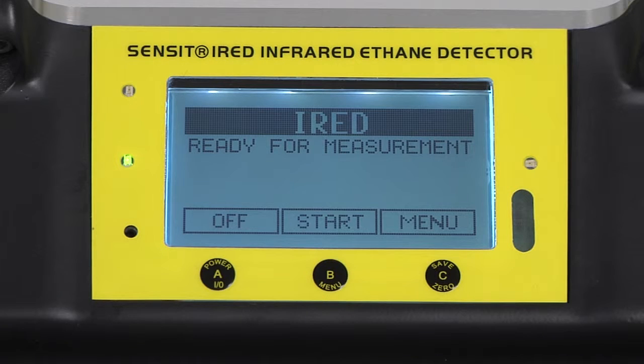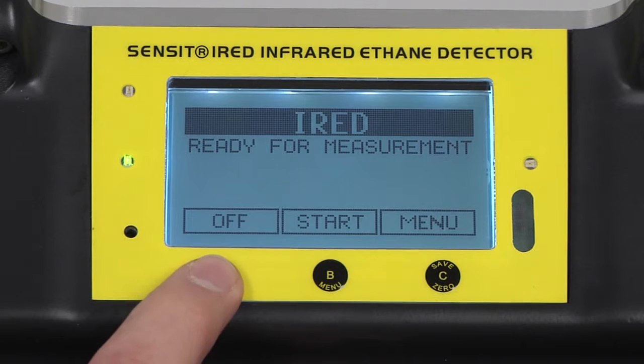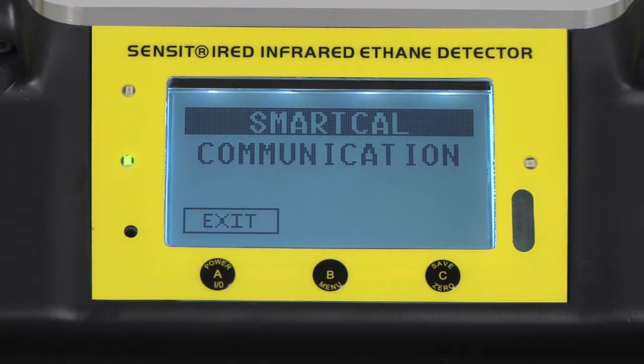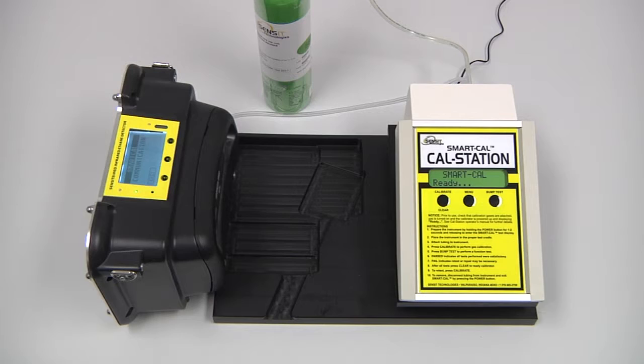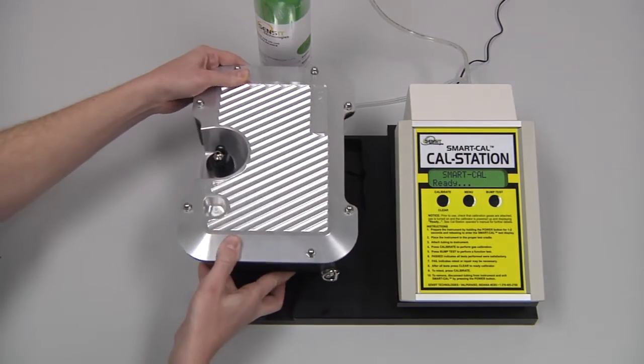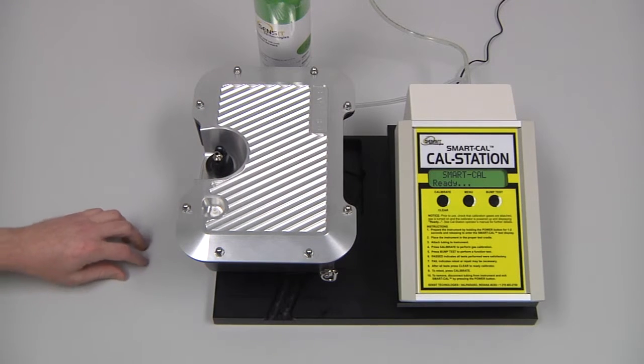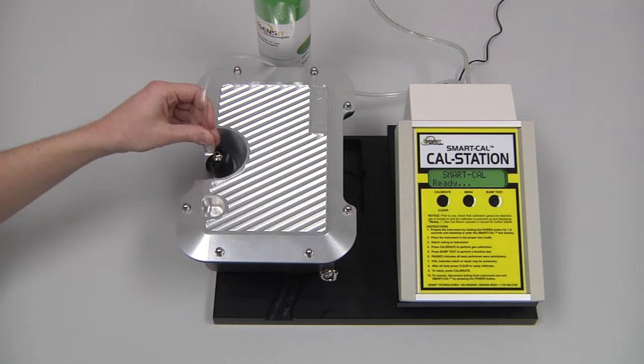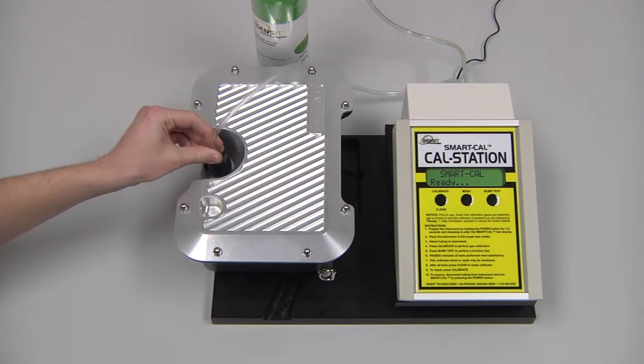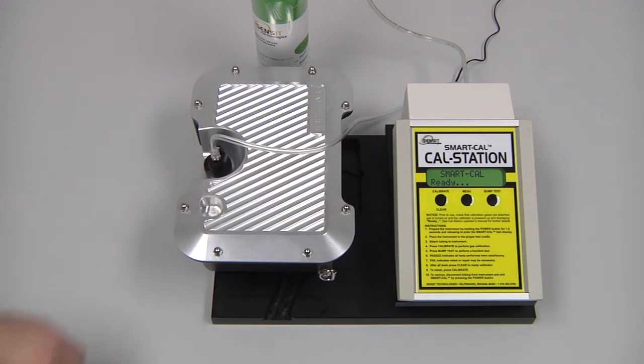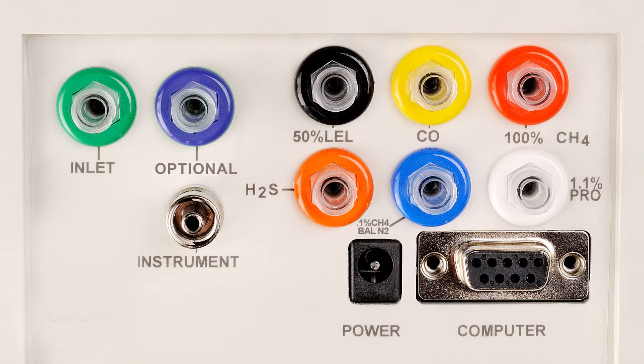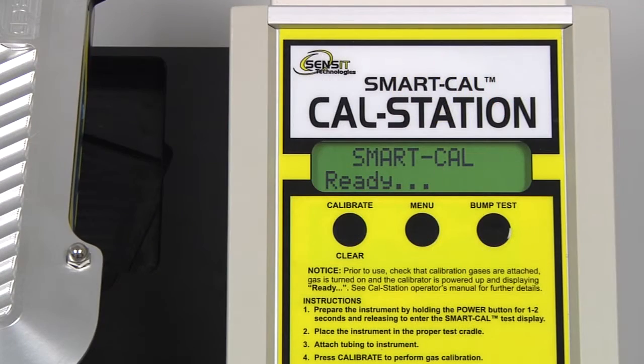After the IRED has completed its warm-up process, we need to enter into the SmartCal mode by pressing and releasing the A button. Next, place the IRED in the calibration station cradle. Attach the instrument hose to the IRED. And after the calibration gas is attached to the cal station, press and release the calibrate button on the cal station.